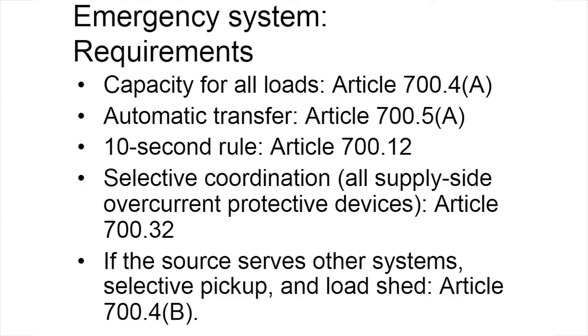The transfer to the standby generation system has to be automatic rather than manual. The emergency system must supply power to its loads within 10 seconds from the moment that normal power fails. That's a very restrictive requirement. Normally, you can expect to see power at best within about 7 seconds if you're using a diesel generator as the standby source.